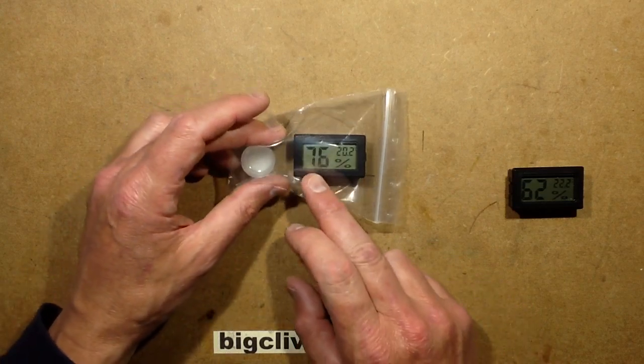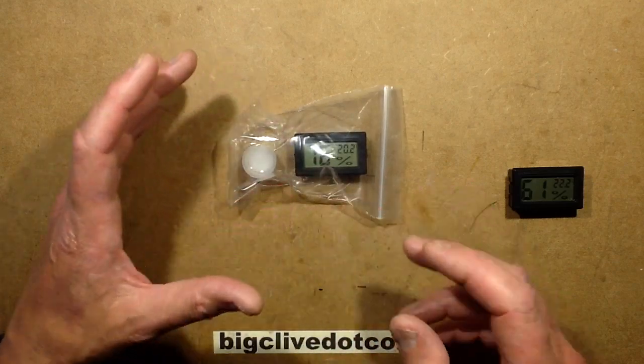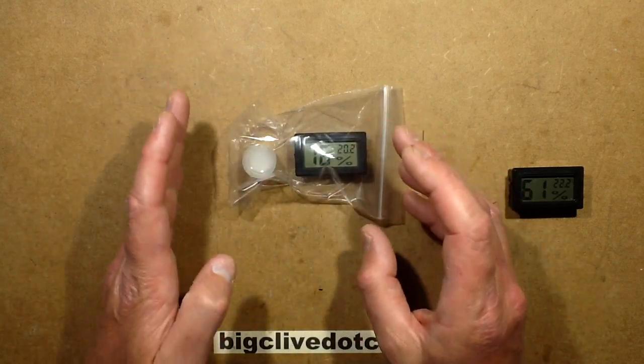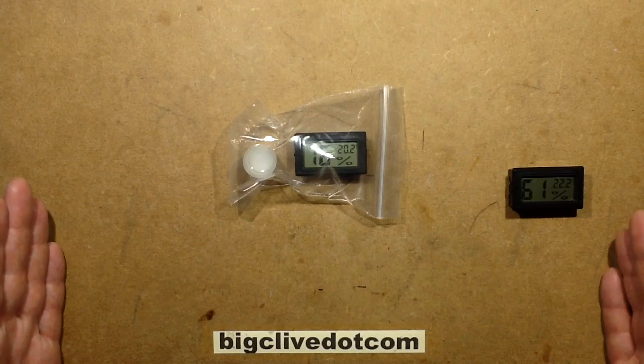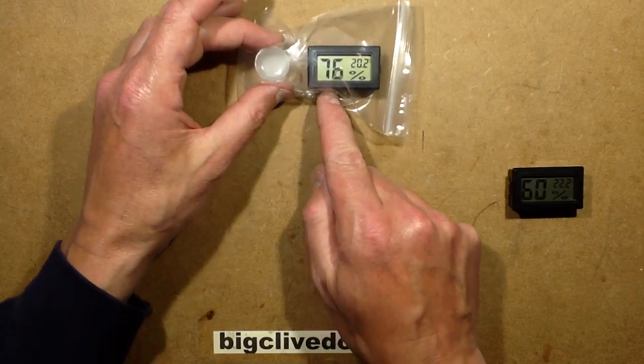It's going to create a humidity in the bag of approximately 75%. In this case it's showing 1% above that — I think it's about 75.5. It's unusual but it's consistent across a wide range of temperatures that it will settle out at this humidity.